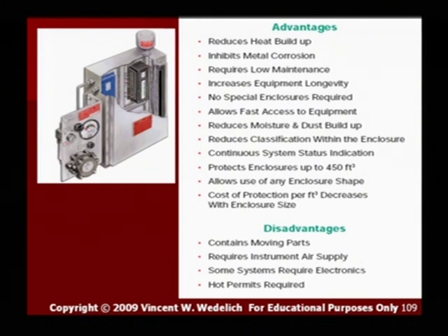The advantages are it reduces heat buildup. That's debatable because I used to make large rectifiers, and I tried everything possible to reduce the heat buildup, and this air contribution from one of these small purge systems rarely does that. But I guess any airflow is better than no airflow, right?